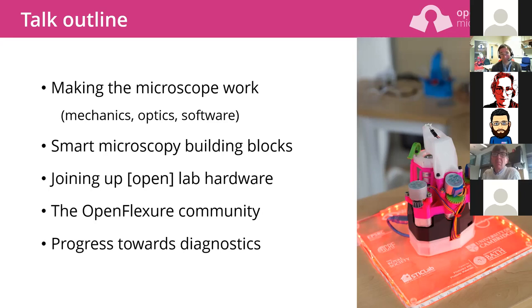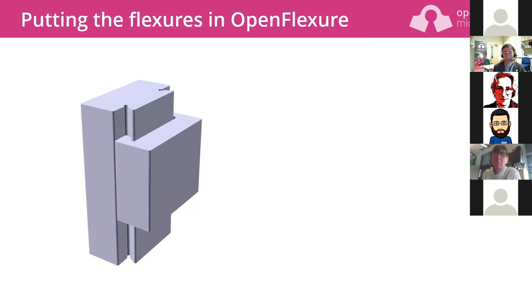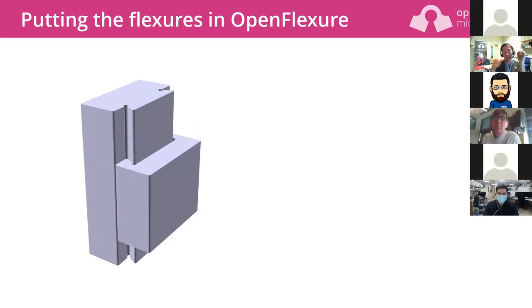The initial contribution of the Open Flexure microscope is the mechanics. The key is implementing a nice linear translation stage — meaning we can move something up and down or side to side without it wobbling in the other directions, without changing angle, without sticking or jamming. Normally that's done with a dovetail mechanism: two pieces of metal, a rail and a slider, one piece fitting tightly over the other, sliding up and down.